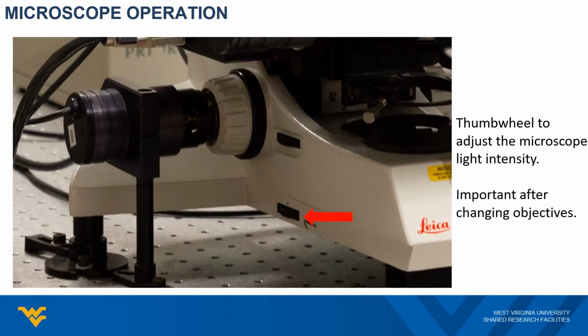To perform Raman measurement, you will need to set those 2 wheels to down arrow and 4. After that, you will only see scattered laser light during the measurement, as shown in the images. Finally, I highlighted a thumb wheel at the bottom left of the microscope. This thumb wheel will allow you to adjust the microscope illumination intensity during the visual sample alignment, which is often needed after changing objectives.